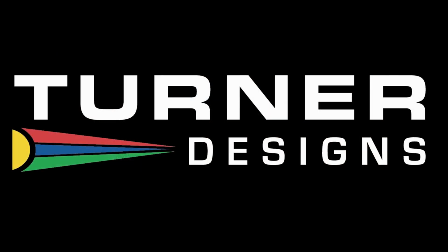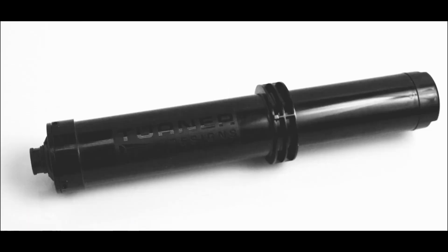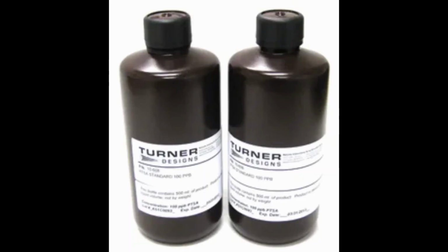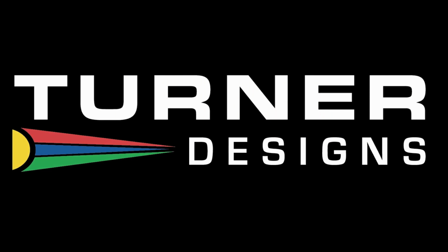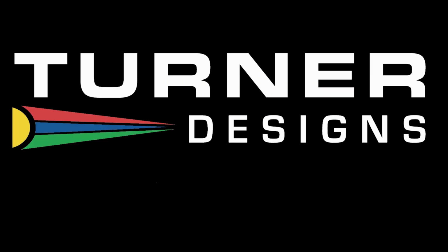If the cleaning does not have an effect on the probe's readings and those readings were off, we recommend double checking the PTSA content with a different LD2. You could also put the problematic LD2 in a known solution of PTSA and see if it's reading correctly in that solution. If the problem still persists, please don't hesitate to reach out to Turner Designs with any questions or concerns.